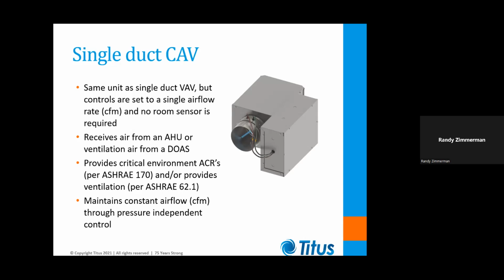And of course, constant volume boxes like that would typically be used for critical environment spaces, like doing room pressurization, for instance. If we want to build a positive or negative pressure in a laboratory or a hospital room, if we put the room under positive pressure, it becomes a protective environment for whatever we've got in the room because we're going to have positive pressure pushing out on the walls.